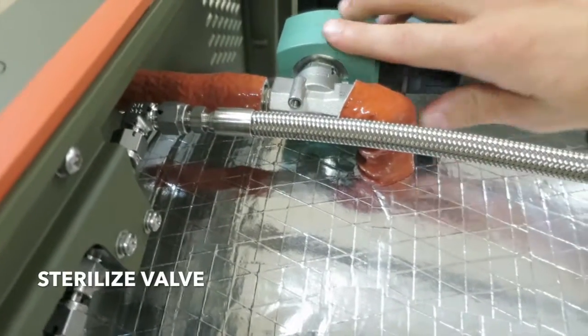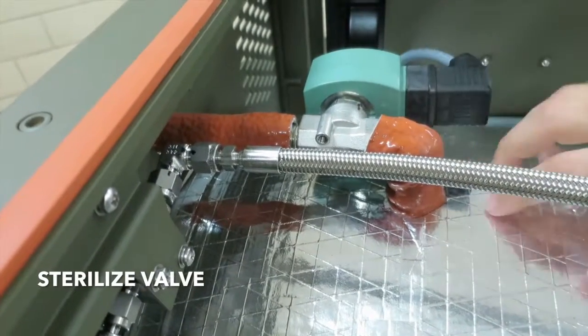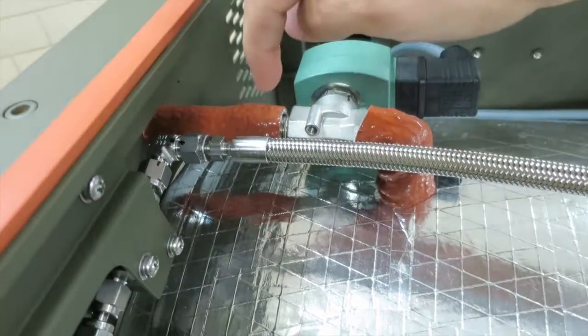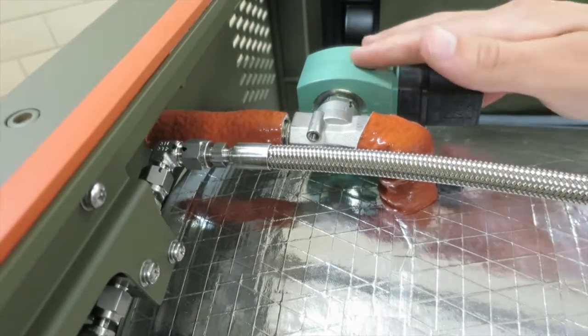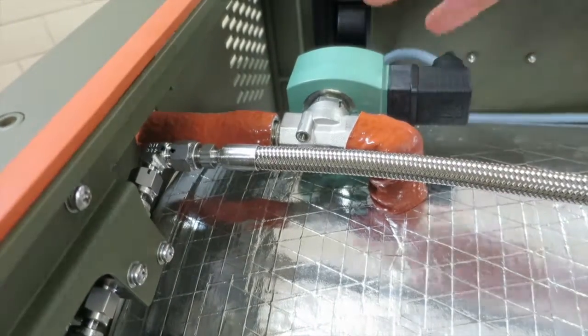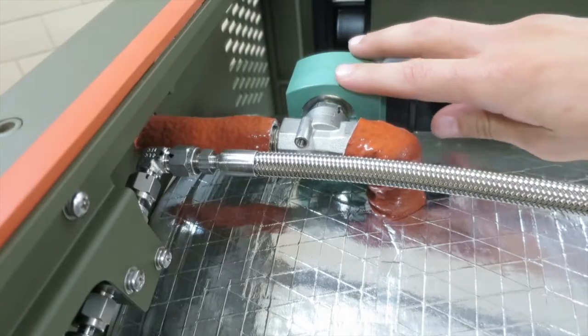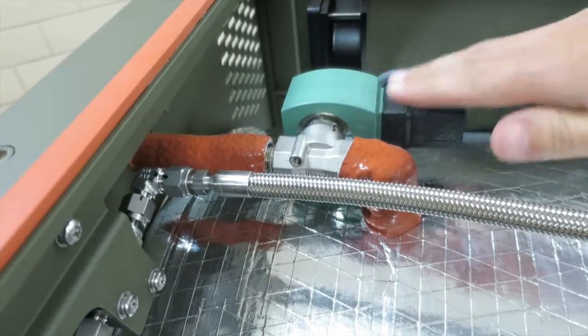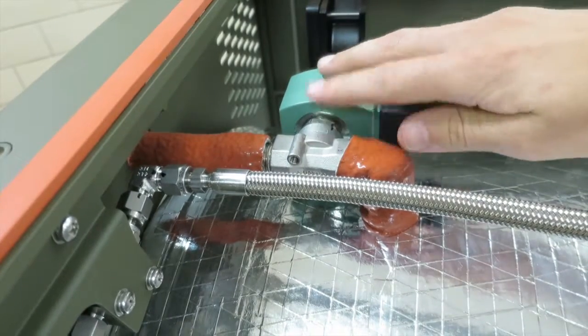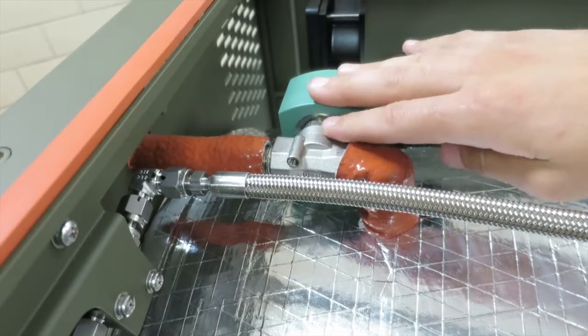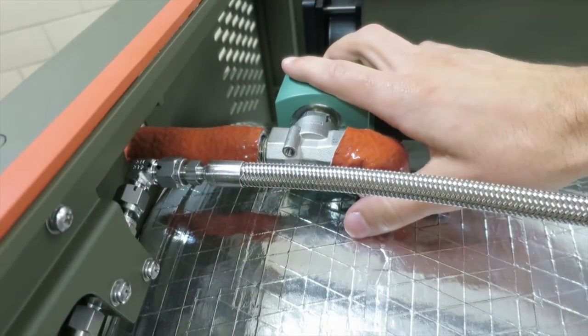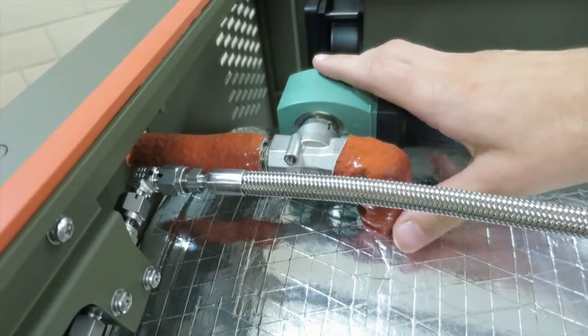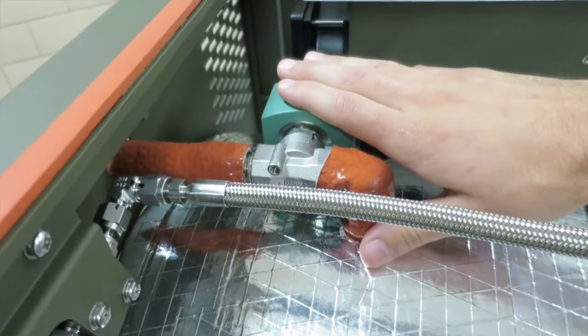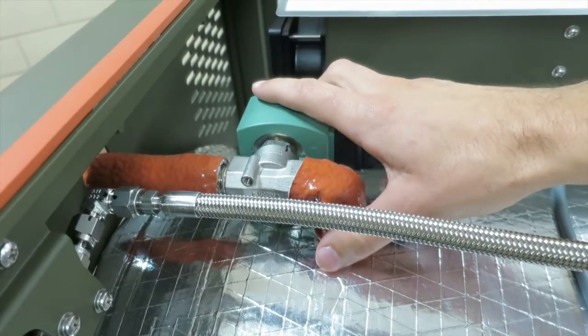Over towards the back, we have the STERILIZE valve. So anytime that steam is jumped from the jacket through this valve down into the chamber, this valve opens. It's a solenoid valve just like the rest of them. So during exposure, this valve is open. During the conditioning phase, when you are doing a steam flush, this valve is open. Anytime you're doing a steam pulse, this valve is open. So this valve is very important to the operation of the sterilizer. Also very important for vacuum leak tests. This valve is very suspect if you possibly have a vacuum leak. So that's it for the top of the sterilizer, and we'll move around to the front and talk about it.